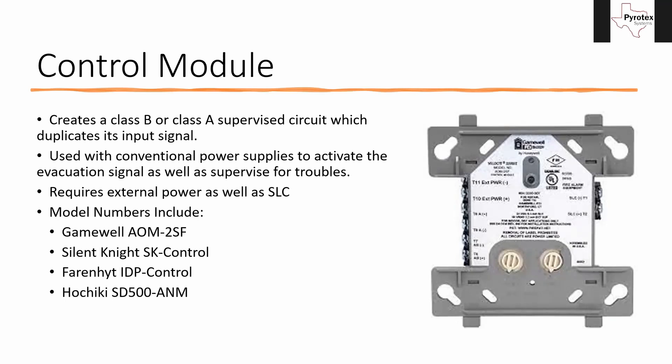We can use it in a high-rise, for example, for speaker circuits — where we hook the amplifier up and send the wire up the riser to hit several different floors. Each floor gets one of these control modules. It comes out of the riser, hits the control module, then goes up to the next floor and hits the next control module, for however many floors that amplifier serves. Coming out of this module, there's a Class B circuit that then controls the speakers for that floor, and it individually supervises it.